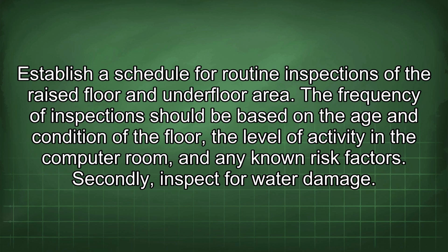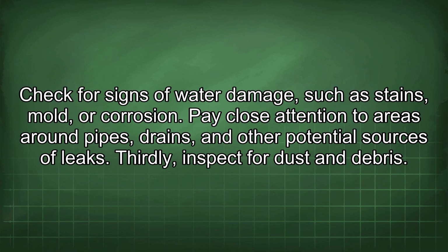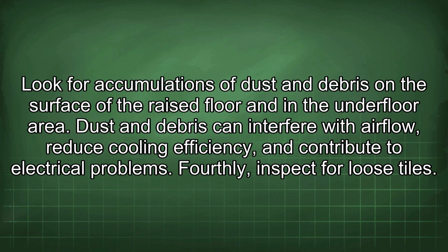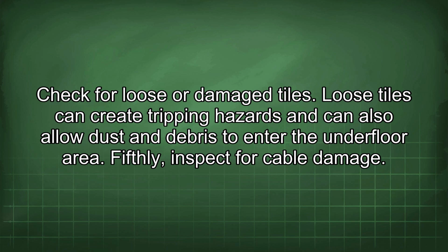Secondly, inspect for water damage. Check for signs of water damage, such as stains, mold, or corrosion. Pay close attention to areas around pipes, drains, and other potential sources of leaks. Thirdly, inspect for dust and debris. Look for accumulations of dust and debris on the surface of the raised floor and in the underfloor area. Dust and debris can interfere with airflow, reduce cooling efficiency, and contribute to electrical problems. Fourthly, inspect for loose tiles. Check for loose or damaged tiles.